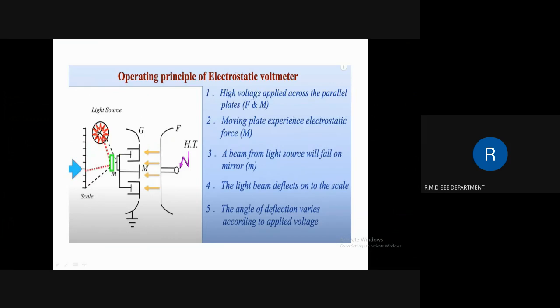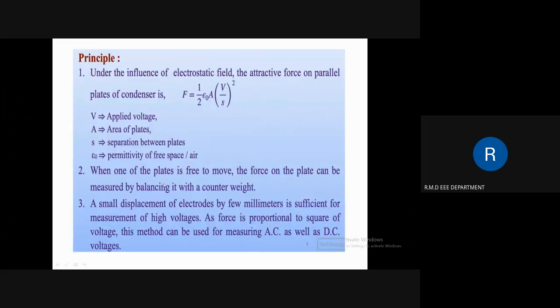In the operation of this electrostatic voltmeter, a high voltage is applied across the plates F and M. The moving plate experiences electrostatic force. The beam of light falls on the mirror and this light beam deflects on the scale. The angle of deflection varies according to the applied voltage.